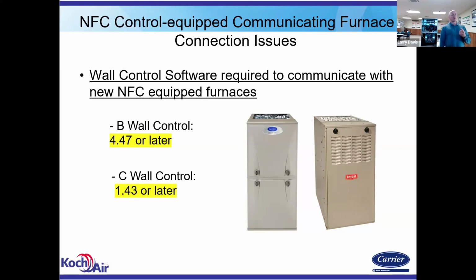There's 2 things you can do. On the B wall control, you can go into demo mode if you have the micro SD card with the 4.47 or later software. You go to your software update in demo mode, plug the SD card in, and you can update it. On B or C, go into demo mode, connect it to the internet, let it connect to the portal, and give it a couple of hours or so, maybe go on about doing some cleanup or other install work. Give it a couple hours to sync up, and then go to software update, and it'll tell you if it sees that the software update's available. Do the update over the air, go through, do a reinstall or power down, power it back up, and it should find your indoor equipment and you're off and running. Okay. But you have to be with either a B or C wall control on the communicating furnaces, and it has to be at those software versions or later.